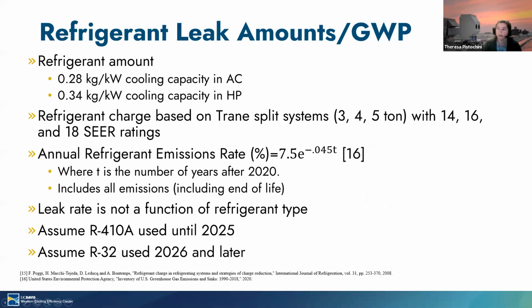So next, we estimate refrigerant charge for an air conditioner and a heat pump. We reviewed manufacturer data for comparable air conditioner versus heat pump models for residential split systems, 3, 4, and 5 ton, of a range of efficiencies: 14, 16, and 18 SEER. One of the things that's tricky is when looking across manufacturer lines, there is significant variation of refrigerant charge among similar pieces of equipment, suggesting that manufacturers don't necessarily design to minimize refrigerant charge.